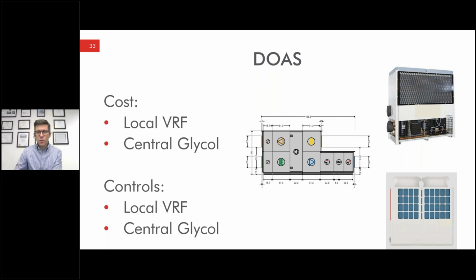So just be mindful of that. But I think the biggest benefit we saw with the VRF solution on the DOAS system was the controls, especially with a 4-pipe or 2-pipe system where you're talking about switchover. Switchover is tough if you're trying to do neutral air from a DOAS system. When the DOAS is on a VRF system, it's totally divorced from that 2-pipe loop. It can do whatever you need to at the coil within the unit, allowing you to provide tempered air year-round without any concern for outdoor air conditions or what the 2-pipe loop is doing. So ultimately, on both buildings we ended up with a local VRF coil at the DOAS, and I think that's a nice solution for these two buildings.